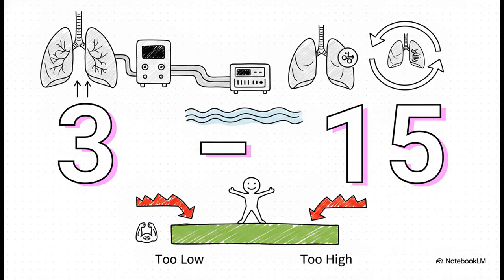I really want to highlight this specific number because this is the absolute Goldilocks zone for patient muscle effort. Think about it. If the ventilator gives too much support and the patient's effort drops below 3, they risk rapid disuse atrophy of the diaphragm. But if the ventilator gives too little support and the effort spikes above 15, they risk load-induced injury. By anchoring the algorithm to this safe range, the autopilot guarantees true diaphragm protective ventilation.